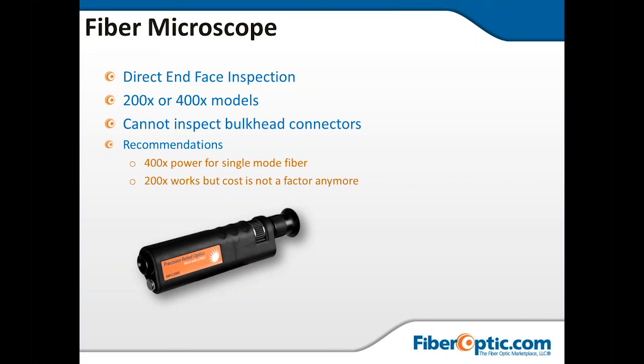A drawback of this type of inspection piece is you can't inspect the bulkhead connectors on the other side of what you're connecting to. It's really good for patch cords, and you can use it out in the field. The other thing is you cannot document what you're seeing, so this is good for a quick check if you don't need to document. It's recommended to use 400X minimum for single mode fiber. You can use 200X, but the cost difference between the two isn't much anymore, so it's worth going up to 400X.